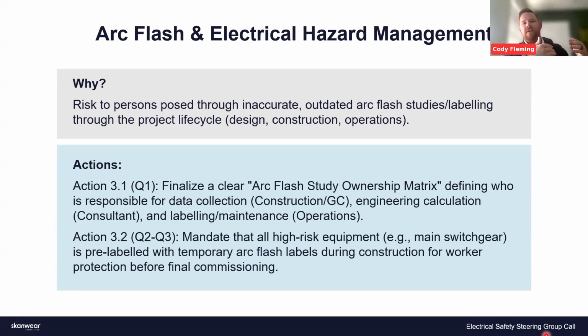How do we account for the fact that we should default to the lower, safer setting, say 15,000? How does that trickle down to the entire system? When these studies are turned over, they come with pre-calculated TCCs showing how fault current behaves throughout the whole topology. So if you adjust one setting based on the make/model requirements of an upstream piece of equipment, how does that impact everything downstream?